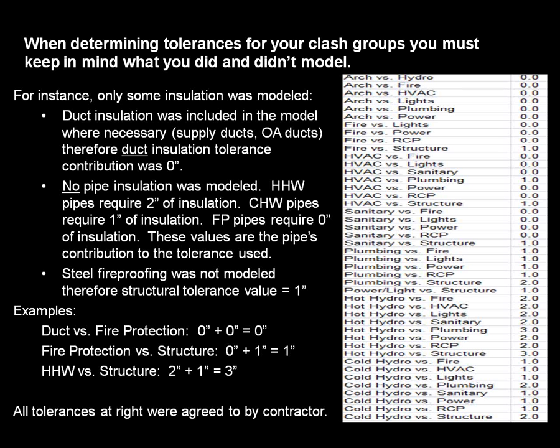So we threw away a lot of clashes by adjusting the tolerances per set clashed against each other. As Tommy said, the pipe isn't just pipe in this model - all the pipe is modeled without insulation. Hot water requires 2 inches, chill water just 1 inch. So using the systems, we varied the tolerance per the things being clashed with each other.